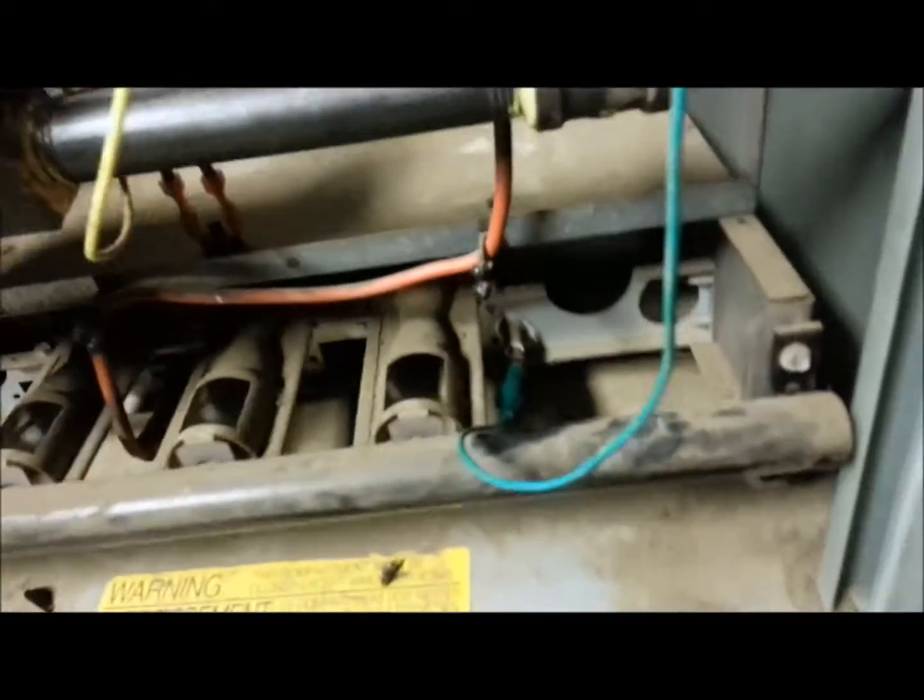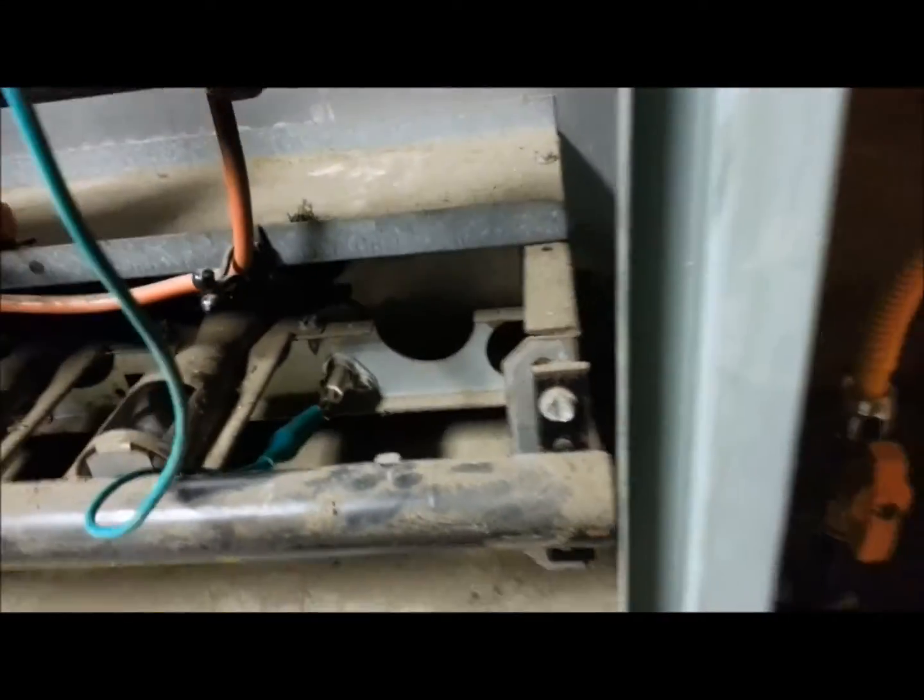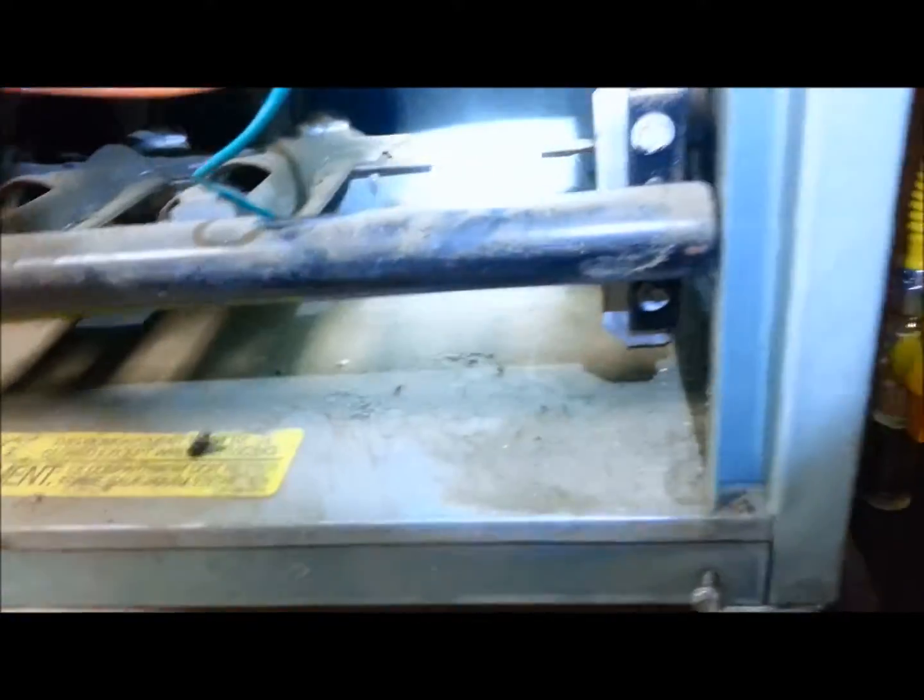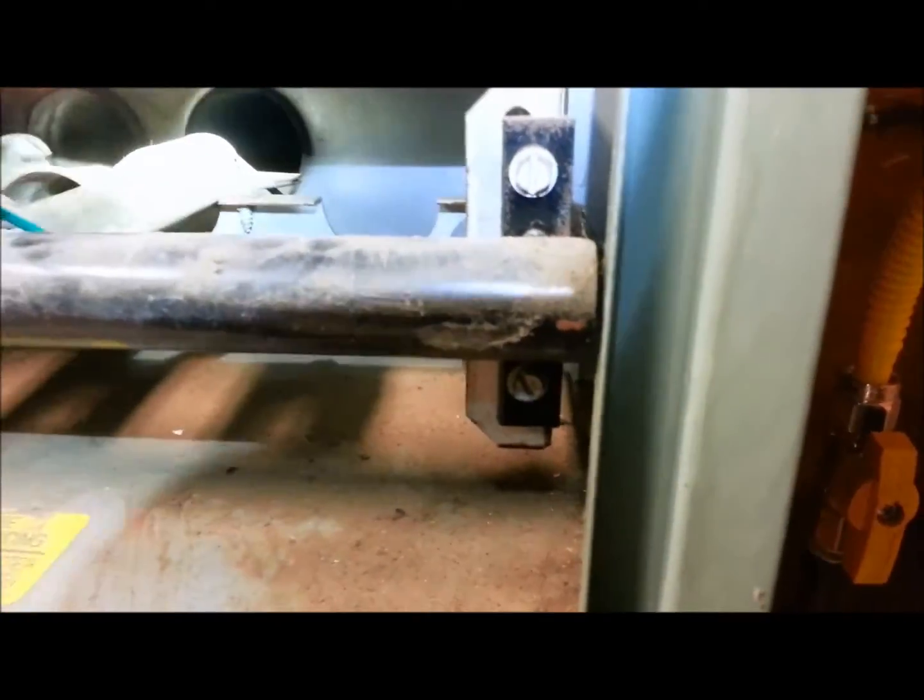Okay, the flame sensor's down there. I've got a jumper wire currently going to it. I'll shine a flashlight on it to give you a better view so you can see the flame sensor there in the back. It's got the wire that goes to it and it sticks over into the flame.